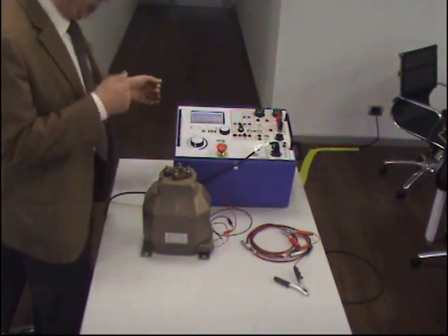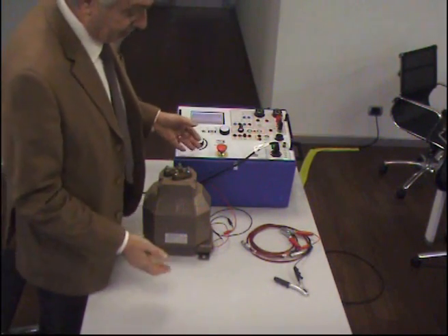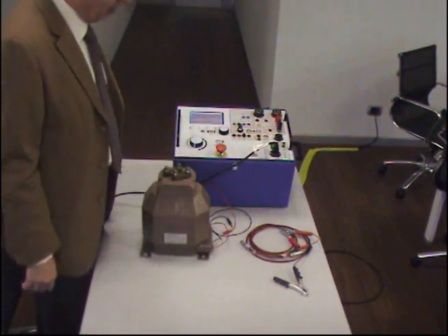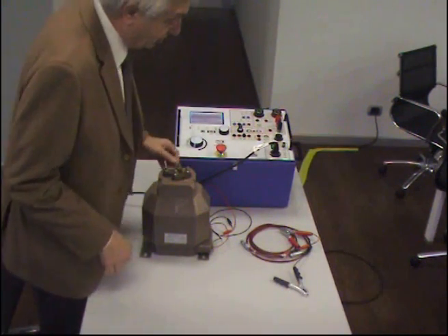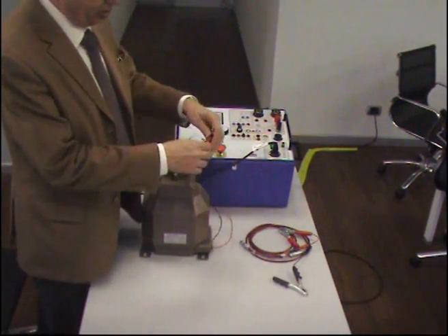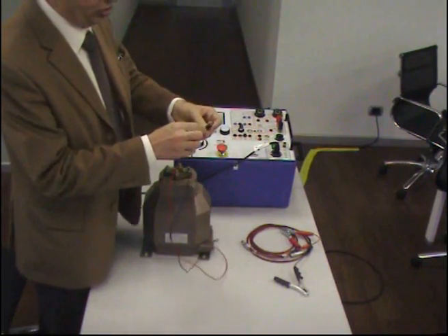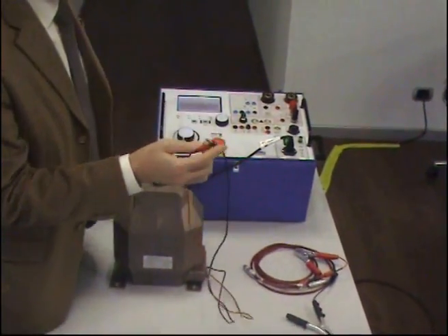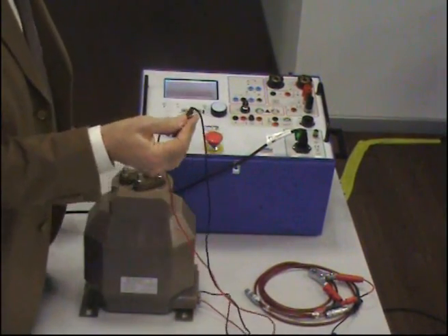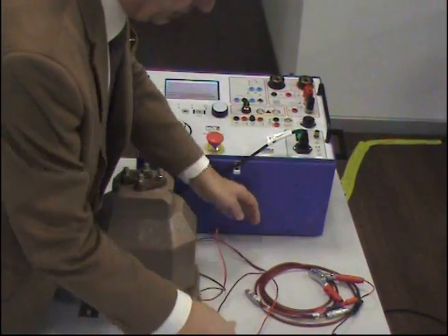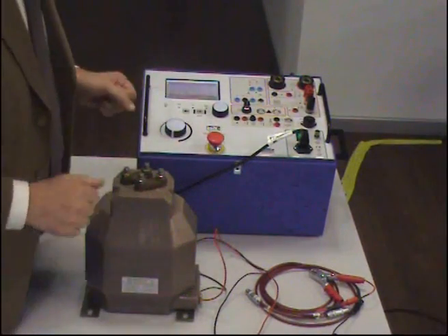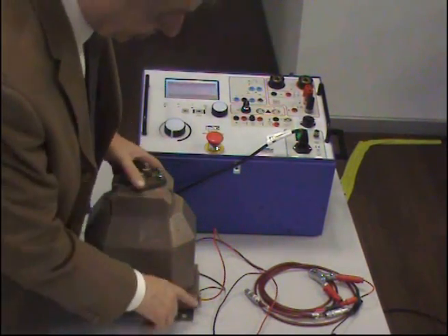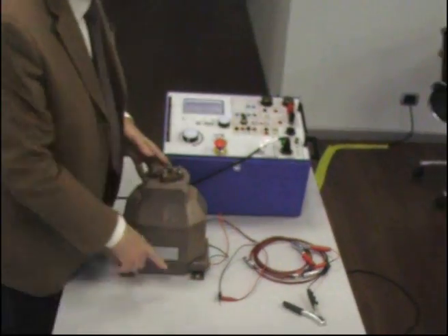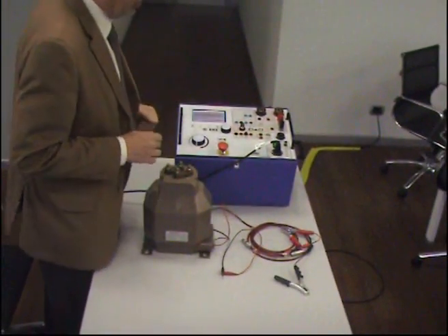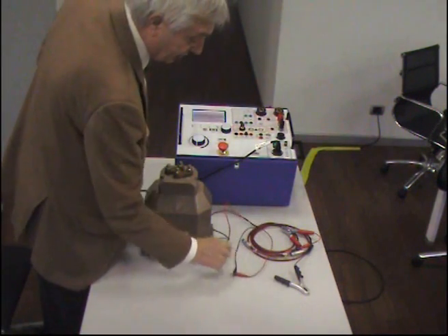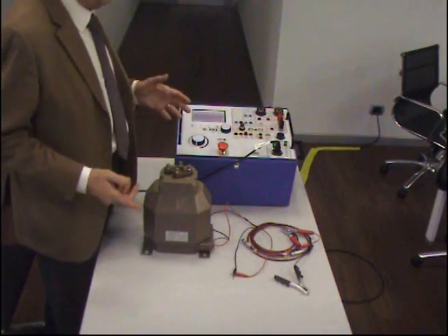This is a lab situation, so I don't have the actual situation for the current transformer, so I will just simulate it. First of all, on the secondary side, I short circuit the winding, because you have to apply the same voltage to both ends. Next, I will simulate that this leg, for instance here, is the ground, and actually it is the ground. So, between this and the ground here, there must be an isolation.